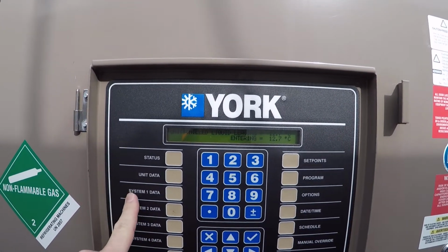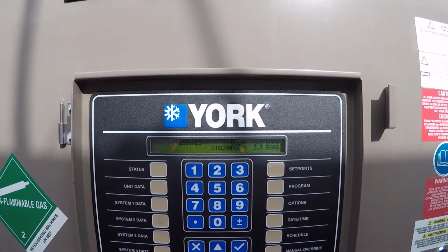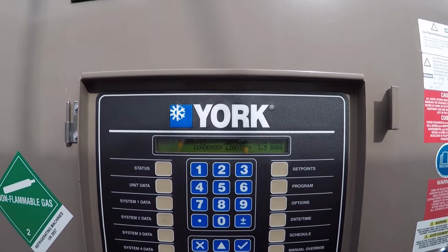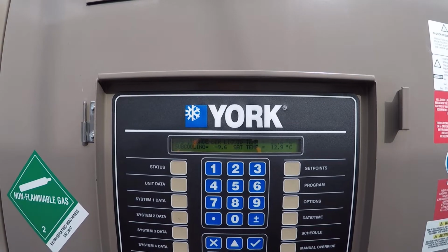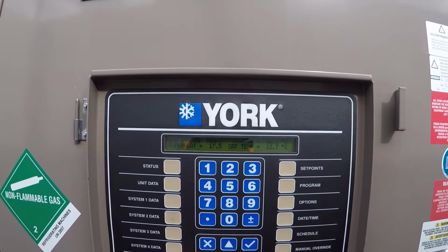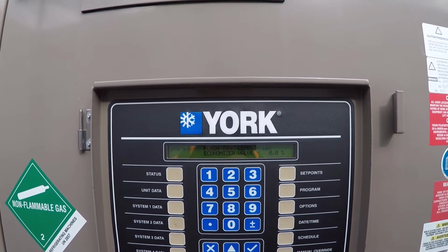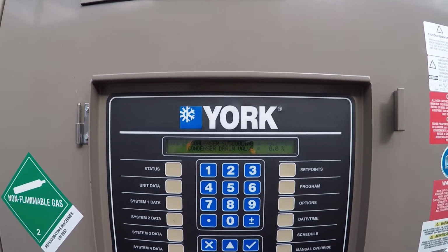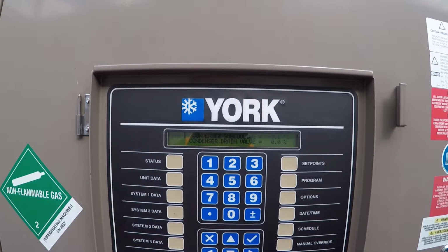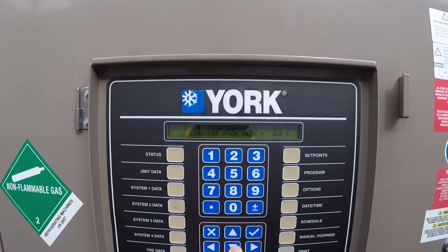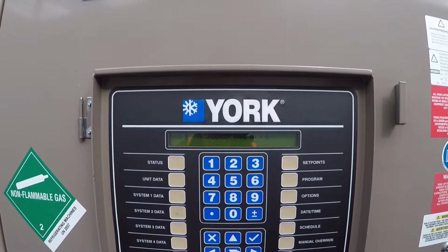And then the next one's going to be System 1 data. This is where you find all your pressures, oil pressure, discharge, suction, and temperatures, discharge, subcooling, and the like. And motor temps, flash tank level, economizer. Like I say, have a bit of a play with these panels. Don't change anything, but become real familiar with them. Condenser fans currently, if you had any that are on.